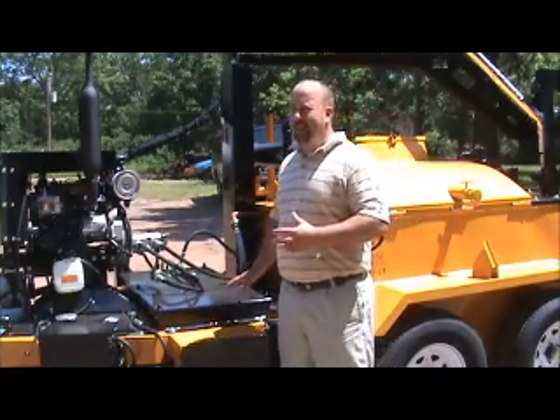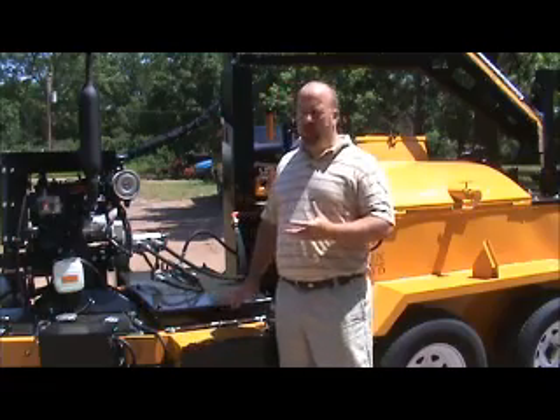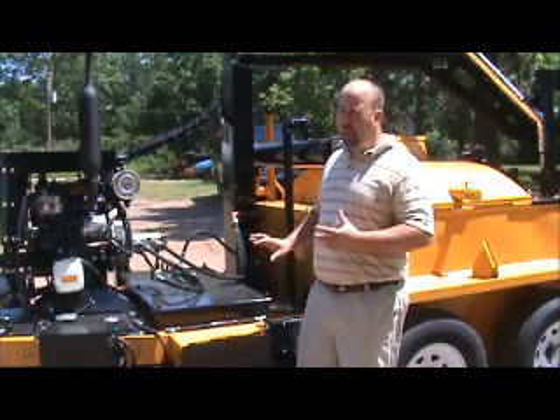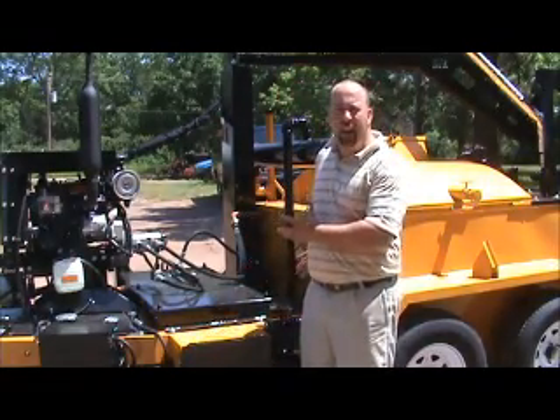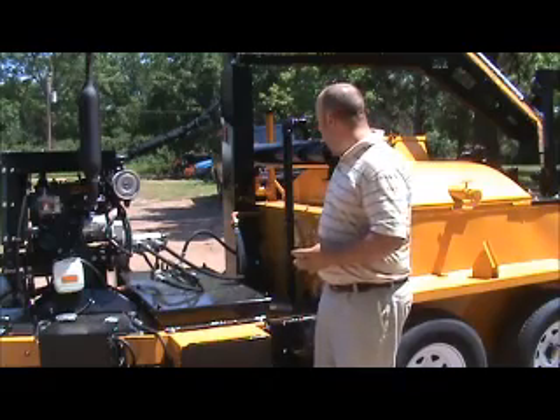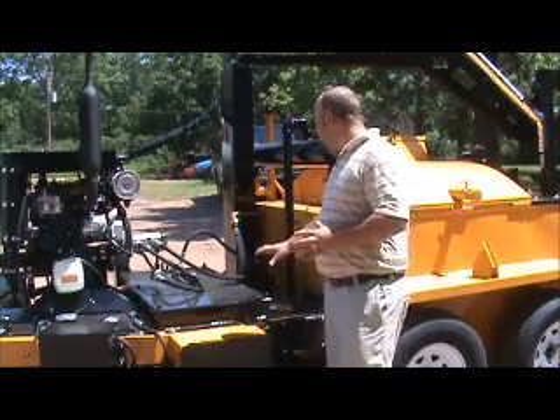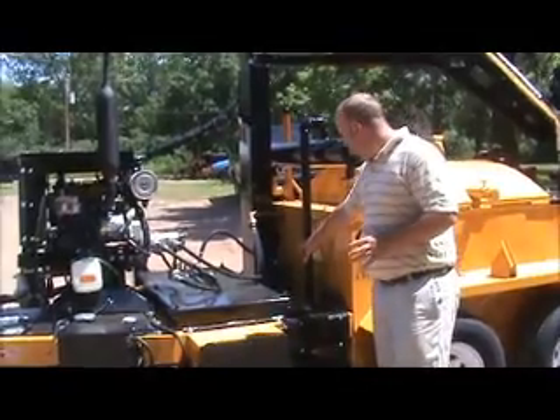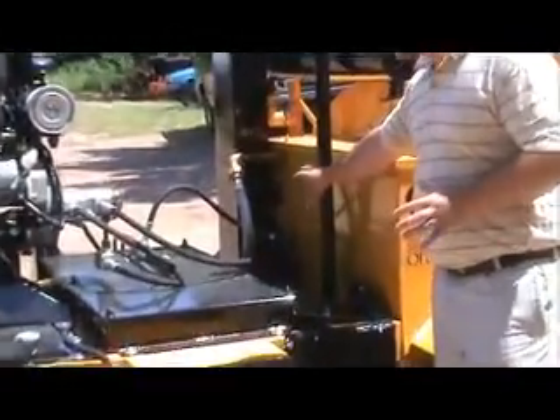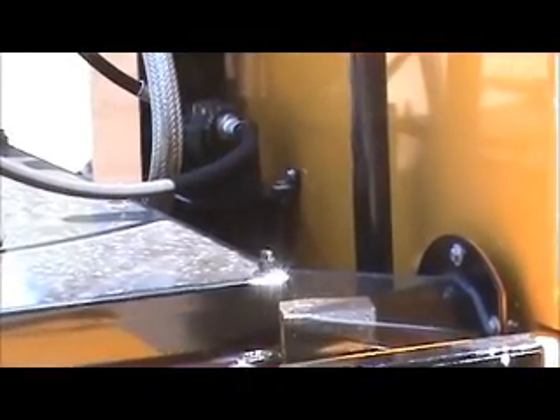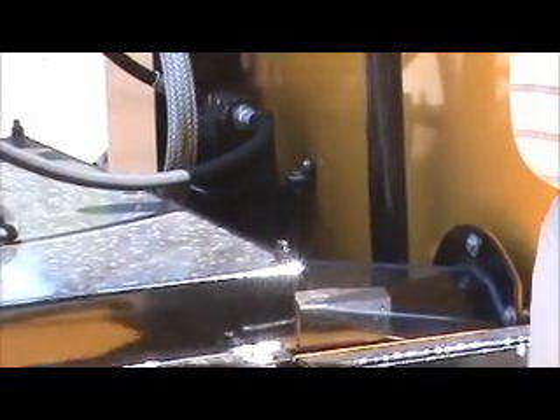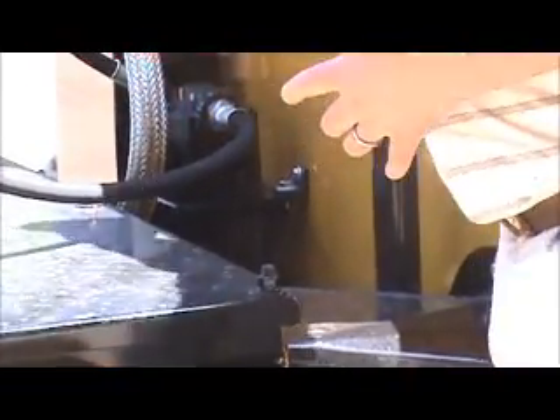This design's been out for a long time. We've had really good success with this, and like I said, it really takes the intense heat off of the main tank. The next thing we're going to talk about, and it's a little tough to see here in the shade, is that we've got a circulating pump on this unit. That circulating pump circulates the hot oil through that coil, and then it dumps. You can see these metal lines here. It actually sends the oil through there.